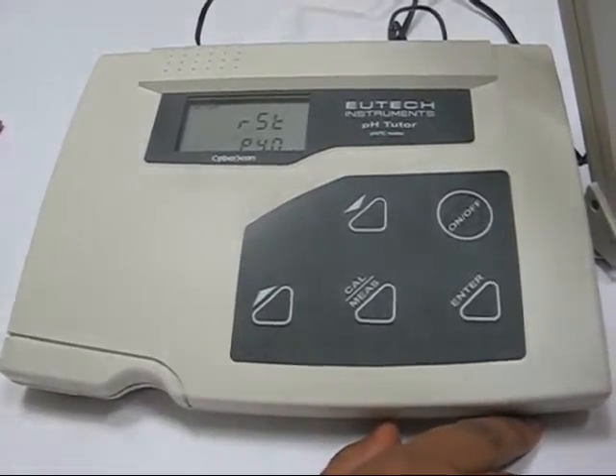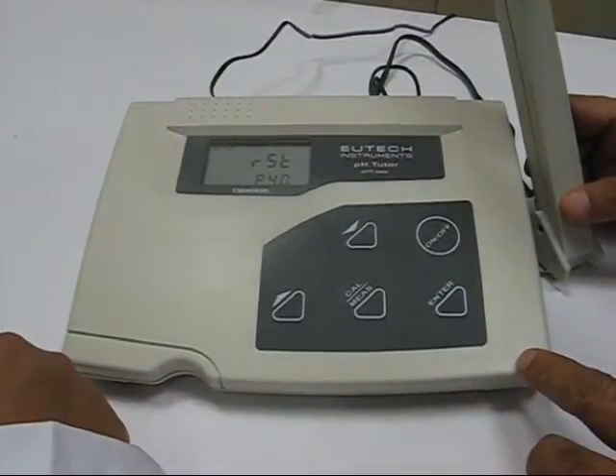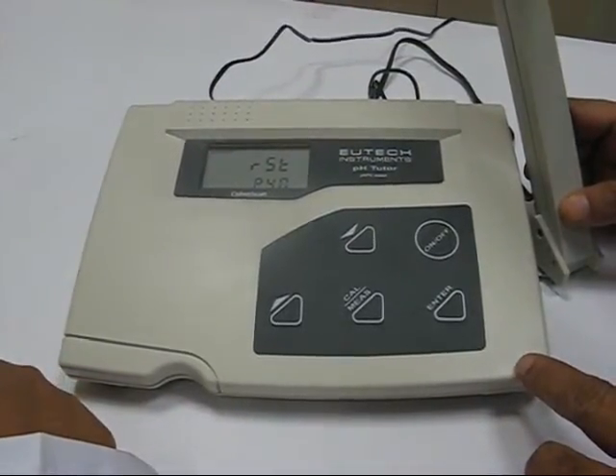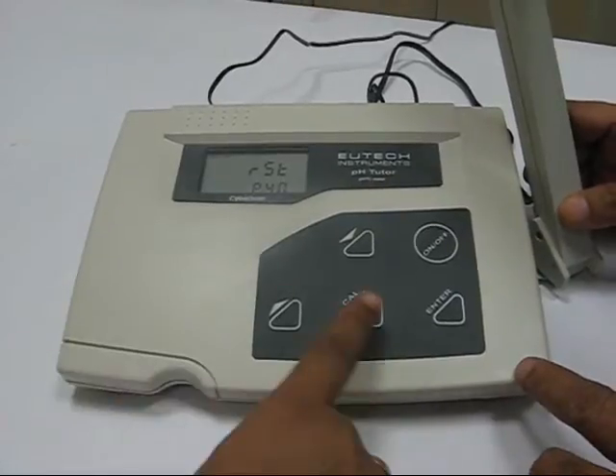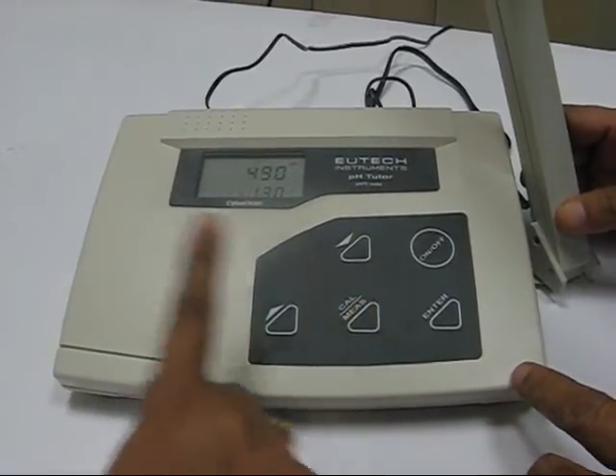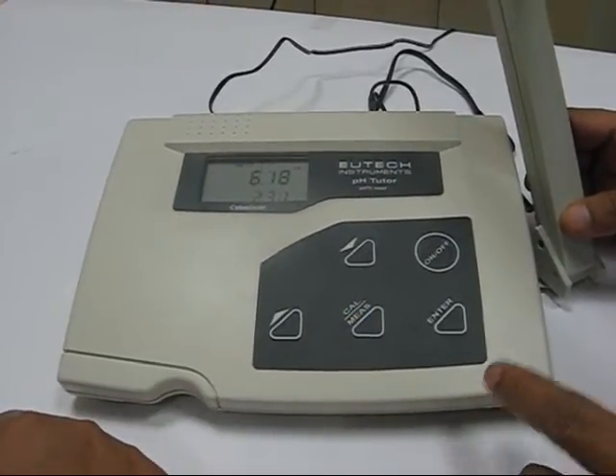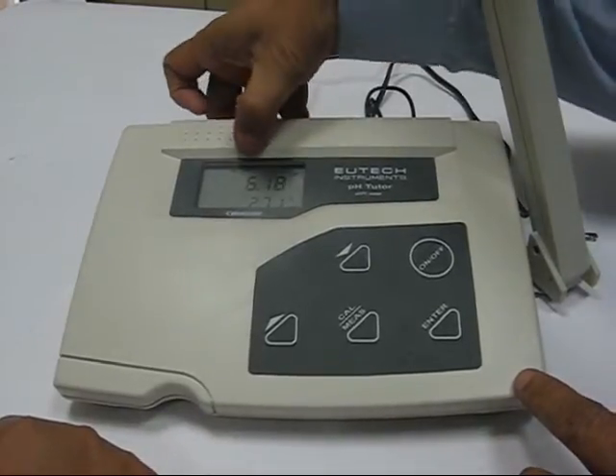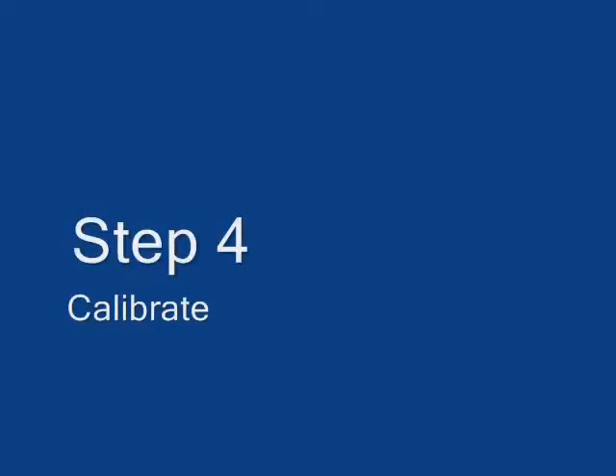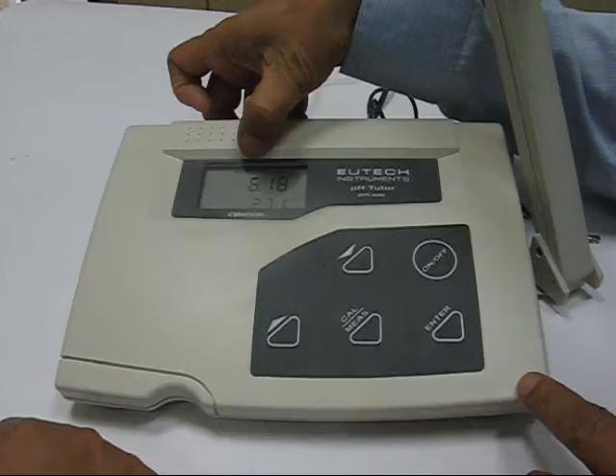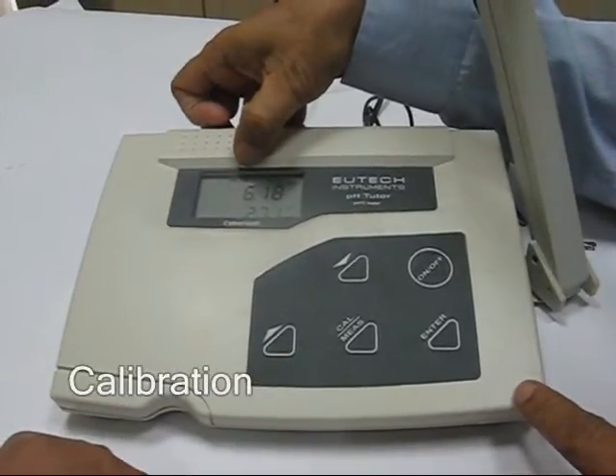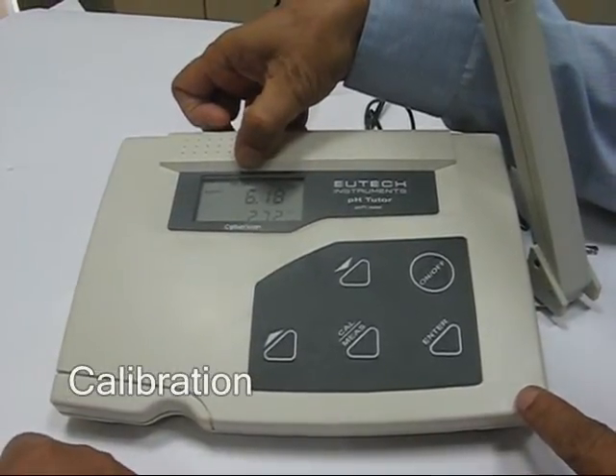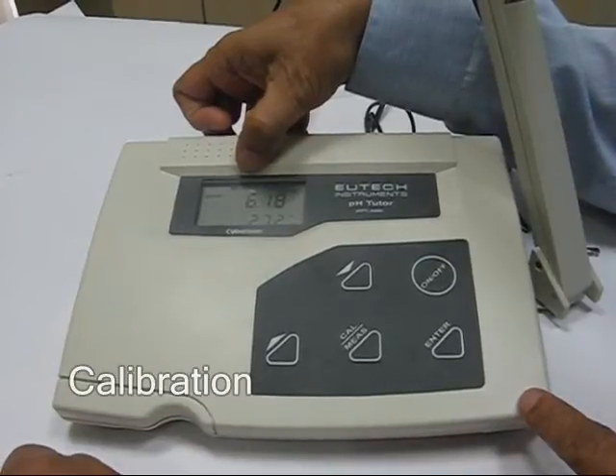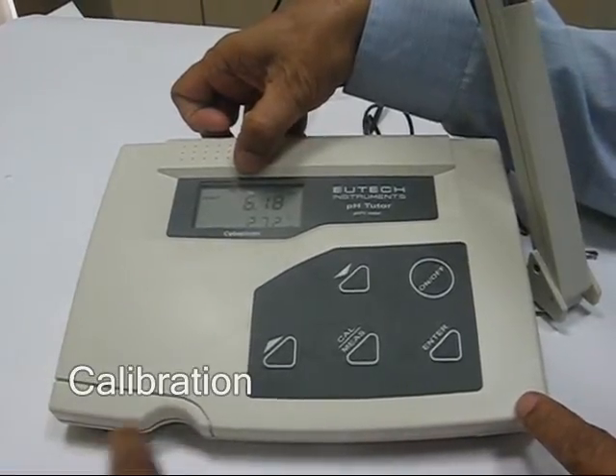Is it clear? Okay. To get to this measurement screen from the setup menu, you have to hit the cal measure key. There you go, the unit resets, and then you come to the measurement mode. Now before we start making a measurement, we have to calibrate the unit with the pH electrode. Let's do that now. Okay.